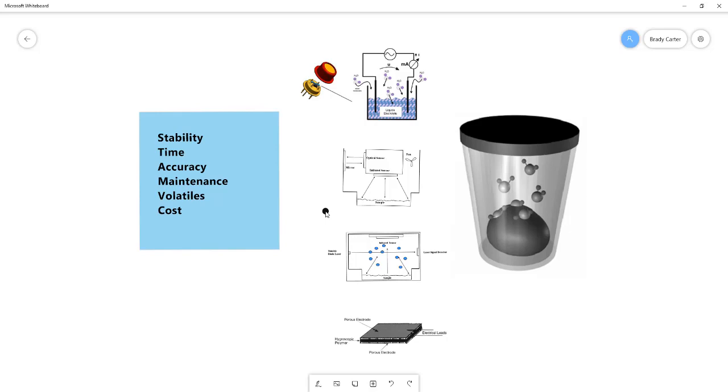The maintenance requirements that are needed to maintain that accuracy are fairly high, as opposed to the electrolytic sensor, which also has a high accuracy. But because the sensor is protected, it's not nearly as susceptible to cleanliness issues. So the accuracy that it's reported can be maintained much easier without having to clean or verify so frequently or make calibration adjustments. The electrical property sensor also is less susceptible to cleanliness issues, but because of the tendency for the polymer's electrical properties to shift and change depending on what's happening, it also needs to be frequently verified and may have to have calibration adjustments as well.